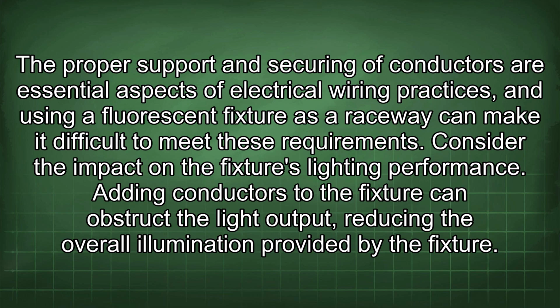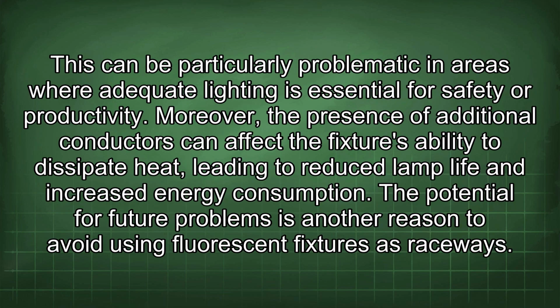Consider the impact on the fixture's lighting performance. Adding conductors to the fixture can obstruct the light output, reducing the overall illumination provided by the fixture. This can be particularly problematic in areas where adequate lighting is essential for safety or productivity. Moreover, the presence of additional conductors can affect the fixture's ability to dissipate heat, leading to reduced lamp life and increased energy consumption. The potential for future problems is another reason to avoid using fluorescent fixtures as raceways.